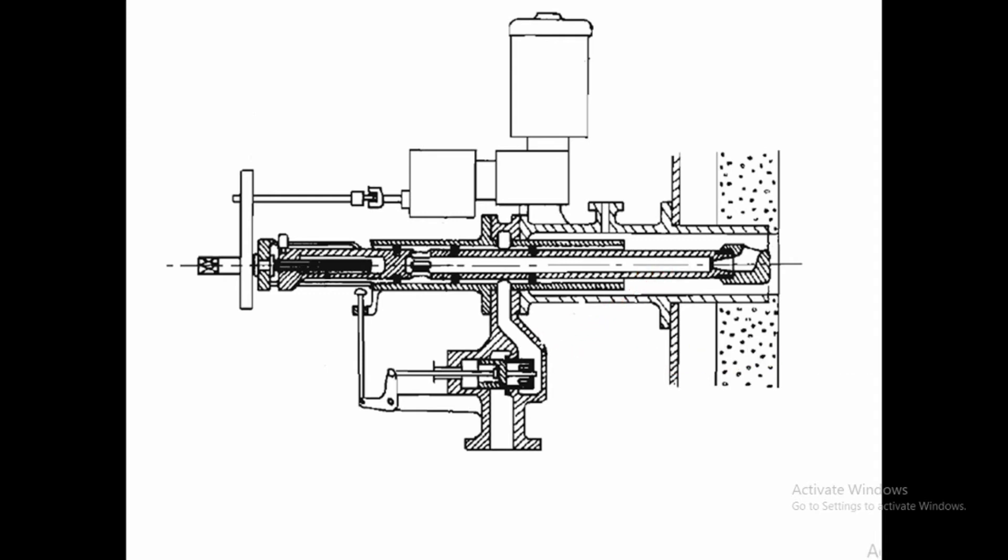On the casing, we see the cooling air inlet. As we pointed, the part of the soot blower. Through this port, the cooled air to the gland box tube is going in. Normally we take in this cooling air from the forced draft fan discharge before the air heater.